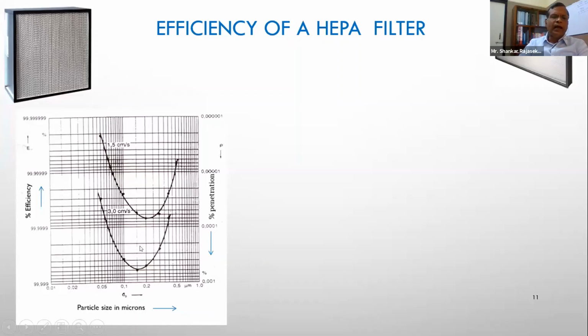And if you look at the normal kind of HEPA filters that we use in the operating rooms, the bottom point normally happens at around 0.15 to 0.2 microns, that band, and it is supposed to give you an efficiency of a minimum of 99.95% at that minimum point. So if you're looking at 0.3 micron size, which we normally talk about, it will be much higher than 99.95.